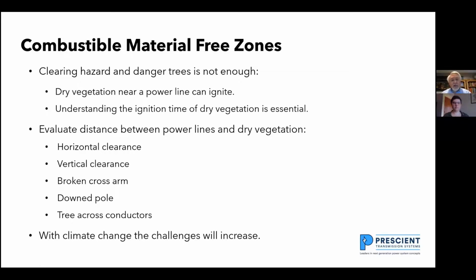I have to look at horizontal clearance, vertical clearance, and then I have to look at the different fault types I can get. I can get a broken cross arm, I can get a down pole, I can get a tree across the conductor. So you should look at all these conditions and make sure that you've evaluated the dry vegetation, the amount of energy you're releasing, and the ignition time of the dry vegetation you have.